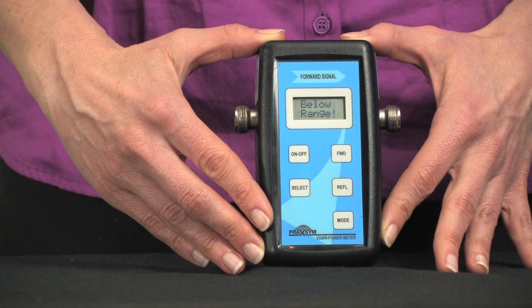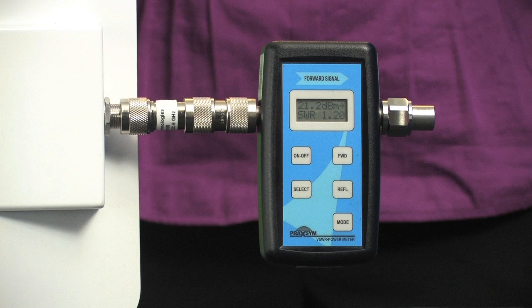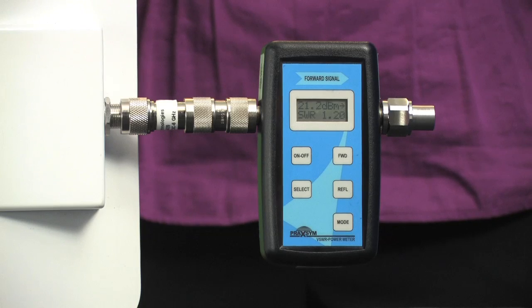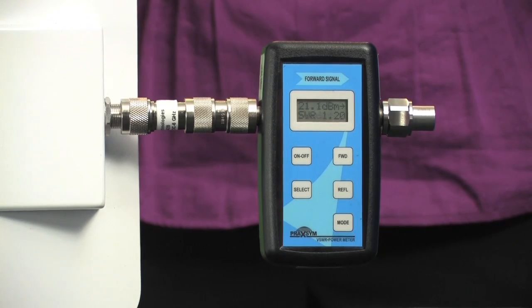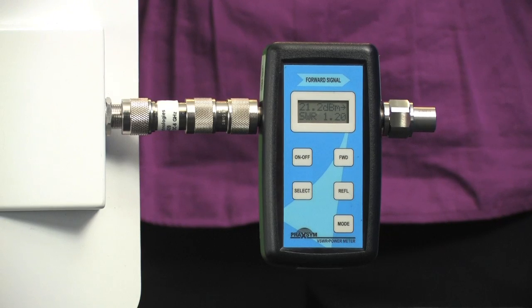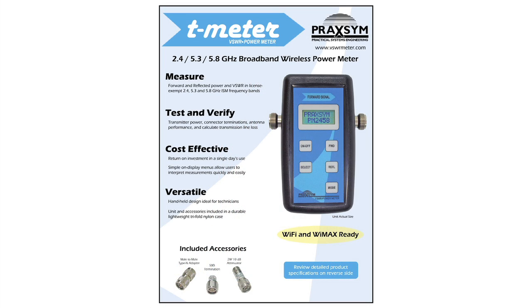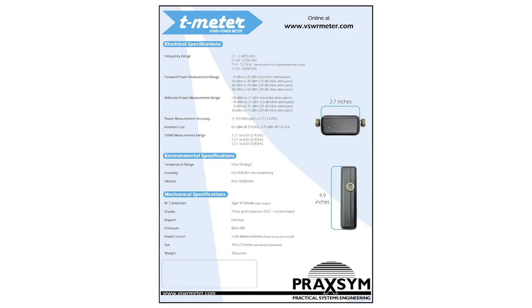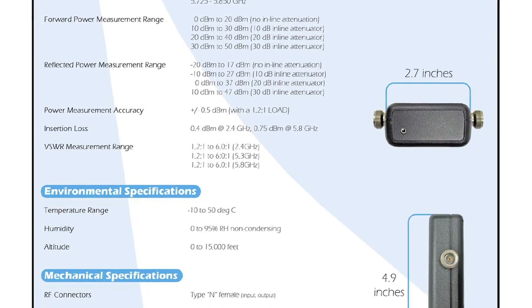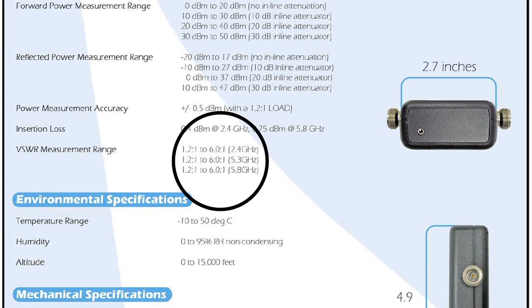Below range is displayed. Once the signal source is connected and the included 50 ohm termination is connected on the output of the T-meter, the display should indicate a VSWR of 1.2 to 1. This is the lowest VSWR measurement the T-meter can make. This particular measurement is a great way to verify that the meter and the termination are operating within specifications.